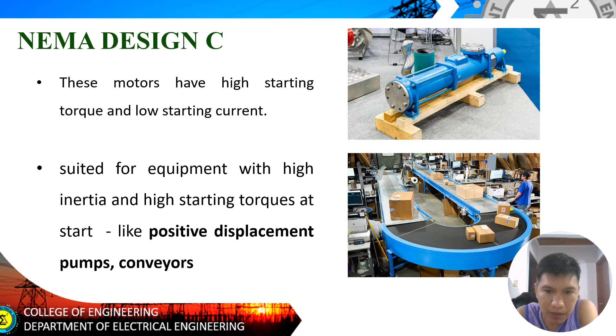NEMA Design C motors have high starting torque and low starting current, suited for equipment with high inertia and high starting torque at start, like positive displacement pumps or conveyors. We usually see conveyors at airports for luggage, which typically use NEMA Design C. Positive displacement pumps also use NEMA Type C.